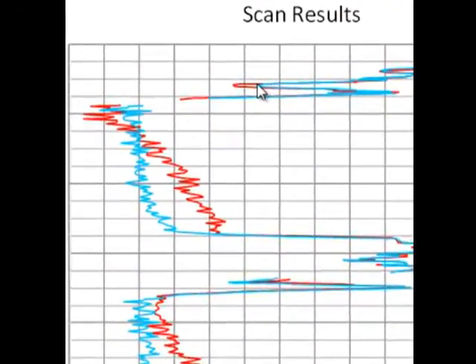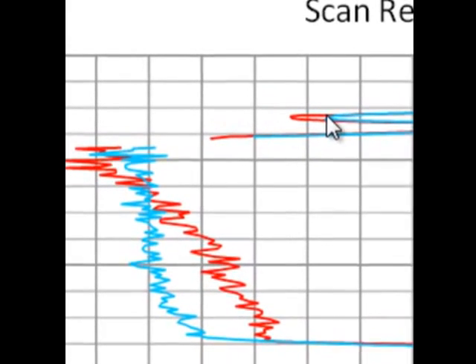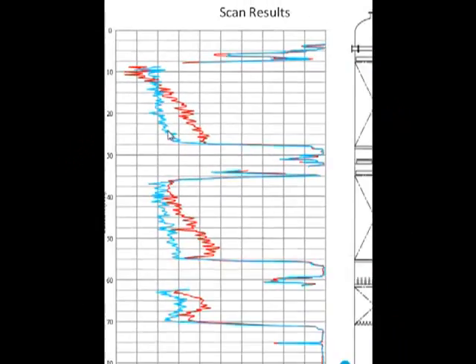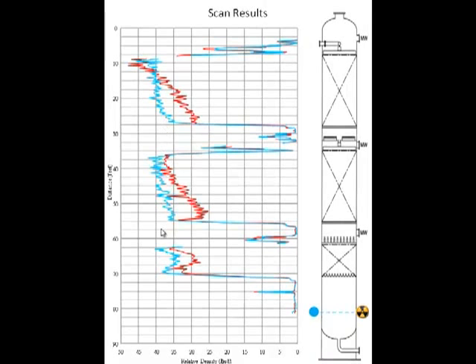In this case, a slight decrease in density was noticed for the top distributor as well as the top two or three feet of the top packed bed. However, the remainder of the tower showed increases in density. Thus, this indicated that the column wash was ineffective. And unfortunately, personnel were required to enter the tower and replace the packing.